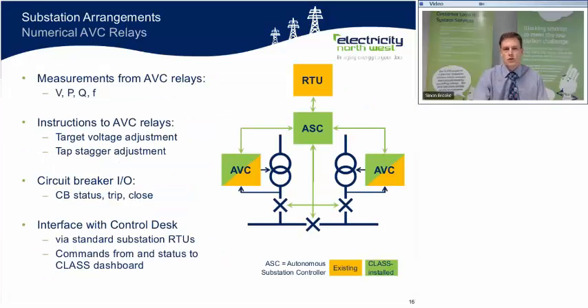So now as I move on to the substation arrangements, if we look at this diagram here, we'll see in the centre the autonomous substation controller in the green box, and this is new equipment that we will install as part of the project. That communicates with the existing RTU on the site to receive commands from the control desk and to issue status back to the control desk.